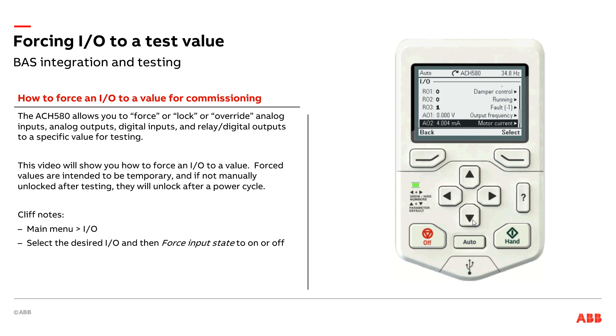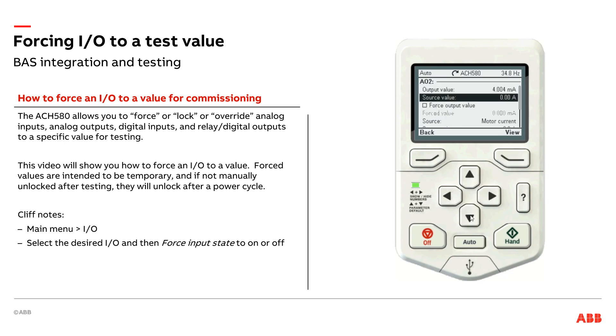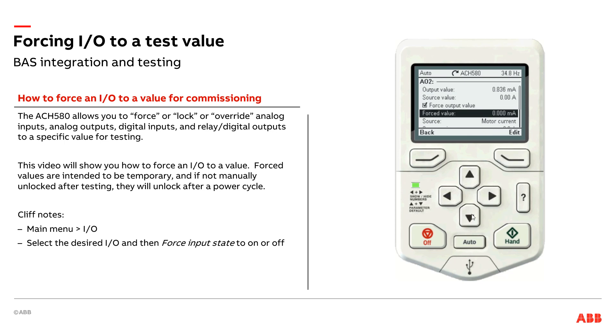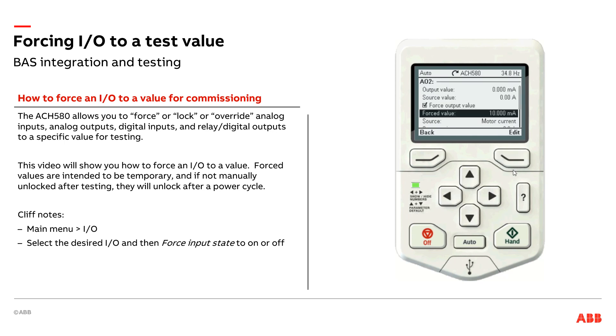I can do the same thing with analog outputs. Just like the analog input where I commanded a specific voltage, with the analog output I can command a specific value. In this case it will be current, because I have it set up for a 4 to 20 milliamp signal. I'm going to force it to be 10 milliamps. Now I can double-check on my building automation system whether I'm indeed seeing 10 milliamps — assuming they have an analog output wired from the drive back to the BAS, programmed here for motor current status. I'll go ahead and release that.